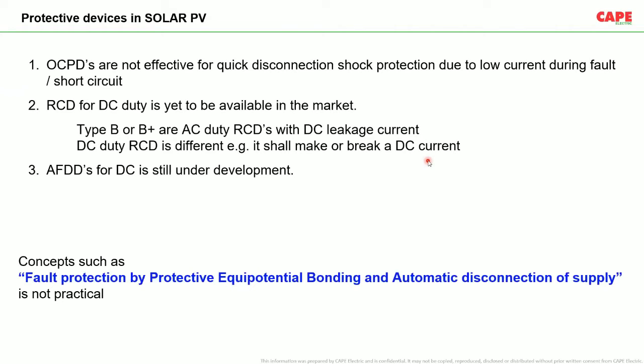The third point is the arc fault detection device, especially for series arc faults. AFDDs are not available for DC application. So with the limitation of the protective devices, a totally different concept has been included in the standard. The general concept followed for an AC application, please don't try to apply it in a solar PV, because, for example, the short circuit current is quite low. The operation time of the protective devices will be quite high. So the normal concepts will not work.